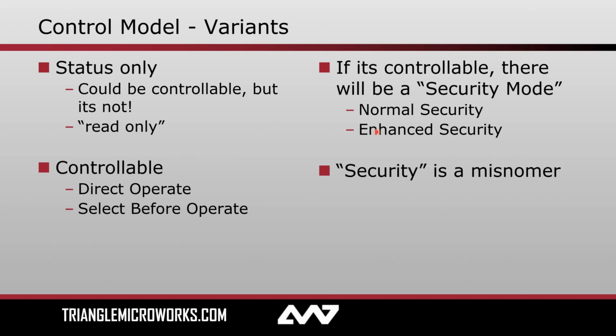In order to know that, for example, the breaker was actually opened, I would need to either issue a read like we spoke about before, or set up a report to contain the status value of that XCBR, that breaker position. With enhanced security, there is included in the response from the server whether or not that command was successful, and if not, why not.